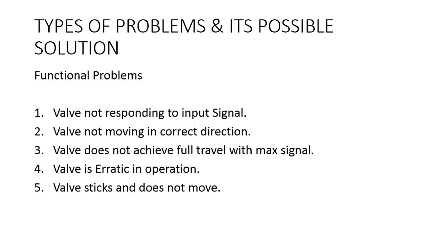Third, the valve doesn't achieve full travel with maximum signal. The actuator can have insufficient travel. The positioner may not be set properly. The actuator may not be connected to the valve properly. These could be three of the problems.